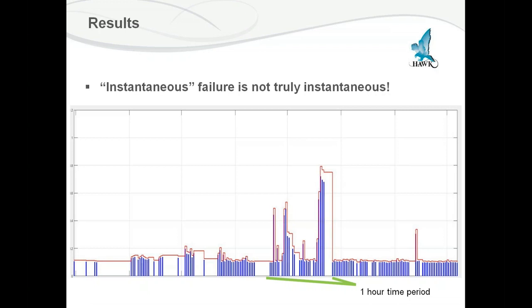You can see our modeling line there. We're starting to get some pretty high readings, even 20, 30 minutes beforehand, when it was probably grinding out, and then the heavy rattles that eventually led to the belt being shut, as you can see there, and then changed out. So even those spontaneous failures that are the bane of the operator, we're picking them up with this kind of technology because we're there all the time.